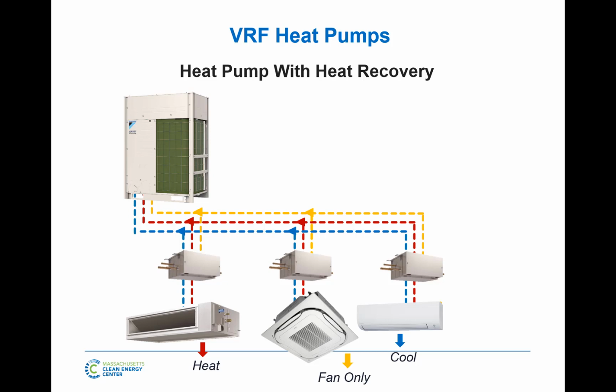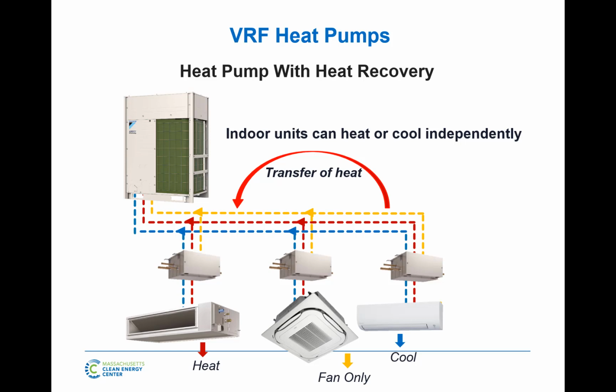Now the good news is, because I'm taking heat from this space and I'm putting it in the refrigerant, and from here I'm taking heat from the refrigerant and I'm putting it in the space, there's a certain level of efficiency there, what we call heat recovery, hence the name heat recovery from the system. It's not perfect, in terms of every BTU of heat from this room doesn't go into that room. It still has to go back to the condenser, go through the cycle and all that, but there's definitely some efficiency gains in doing that.